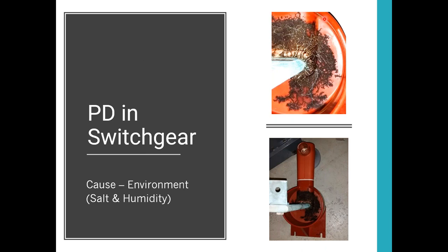Piece of switchgear, heavy, heavy surface discharge, heavy carbon buildup. This is one of the islands, so surrounded by salt and high humidity. They've got known moisture problems. They've got water pooling, almost filling up the bottom of their switchgear. It's an island. It's all sand. It all perks in, goes through the concrete. There's nothing they can do about it. But this is a normal test for them.